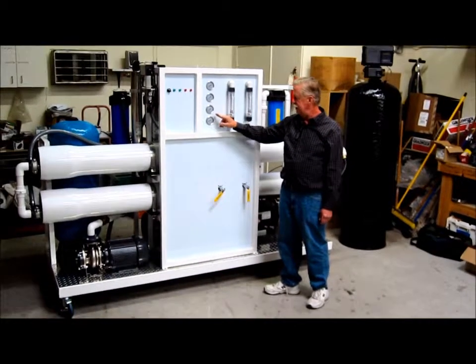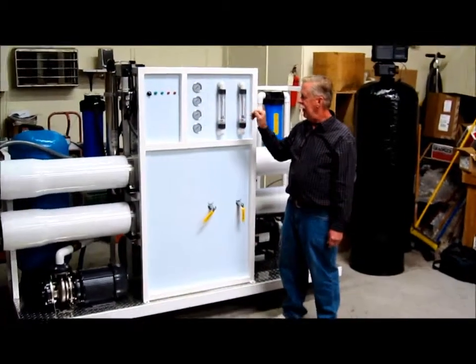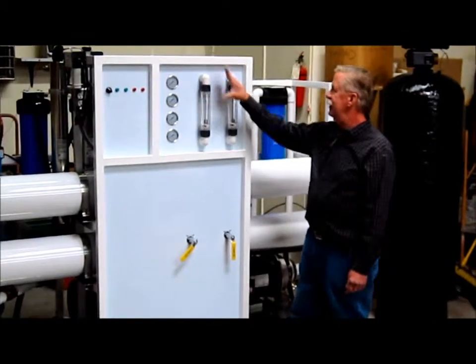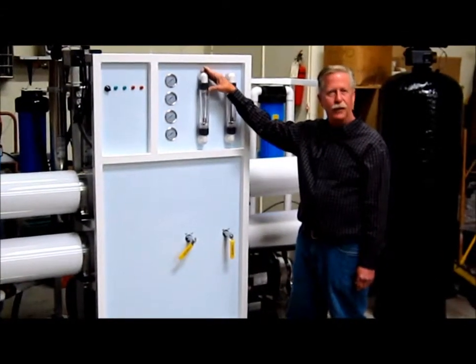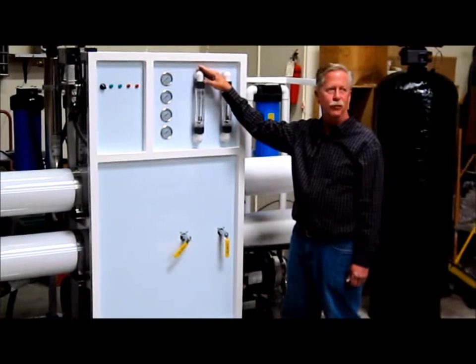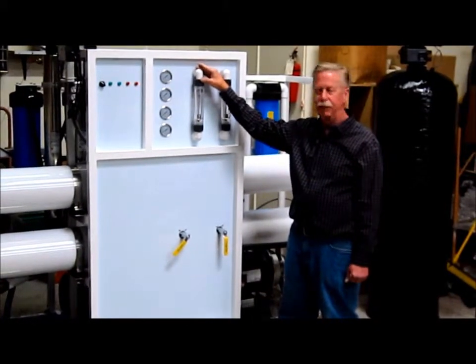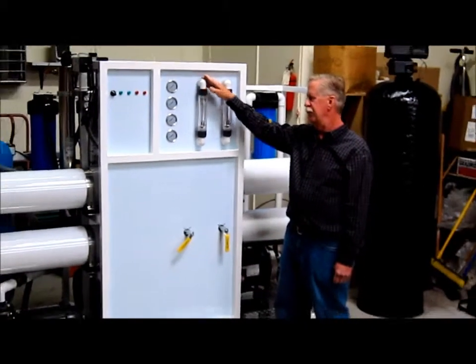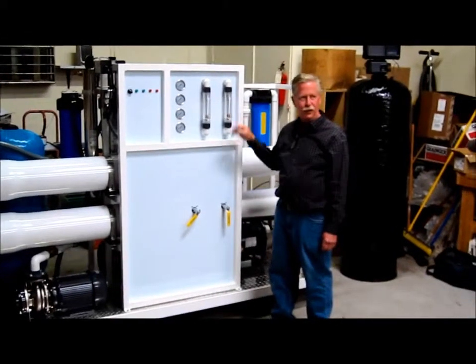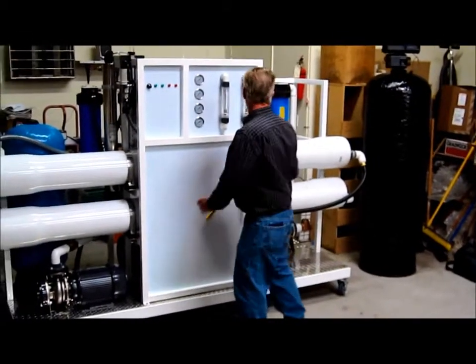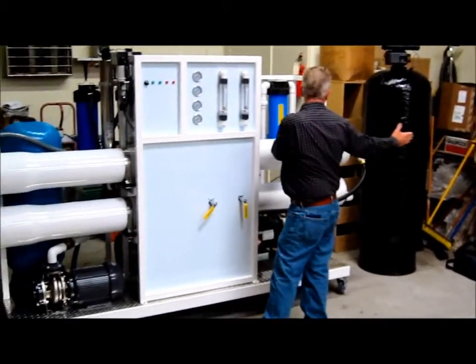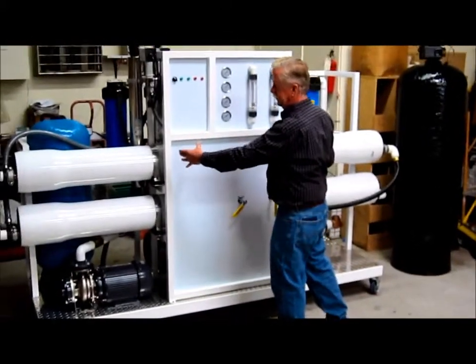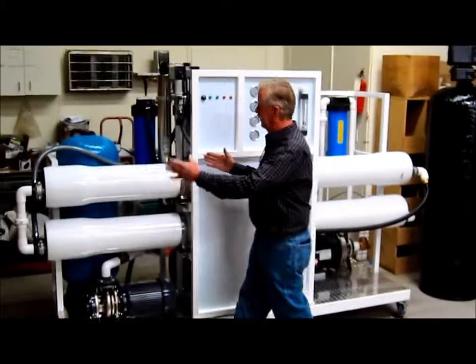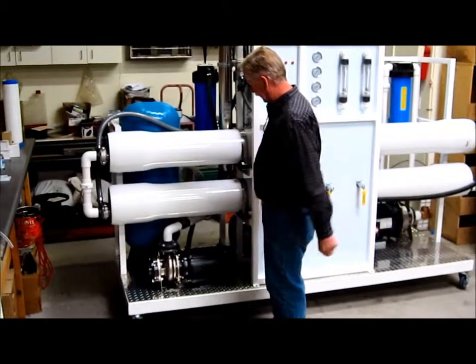Then again, you've got your system pressure, and after the water leaves the flow meter here, the water would go into a pure water storage tank. That's where the water is stored, and you pull it out on demand. Now, we've pre-filtered the water over on this side. We purified basically with the center section. Now over on this side, we have the delivery section.